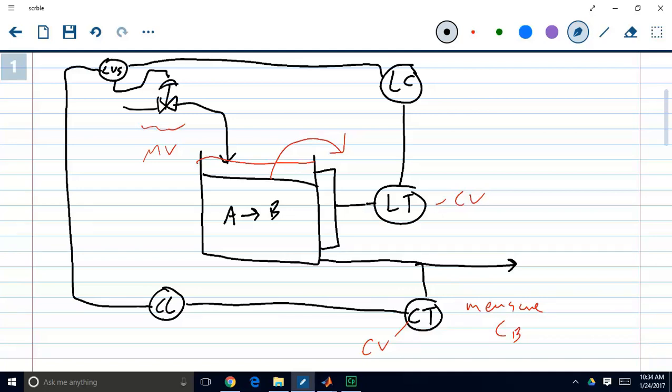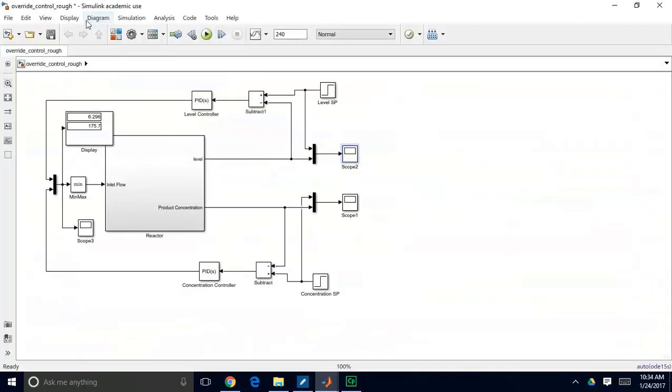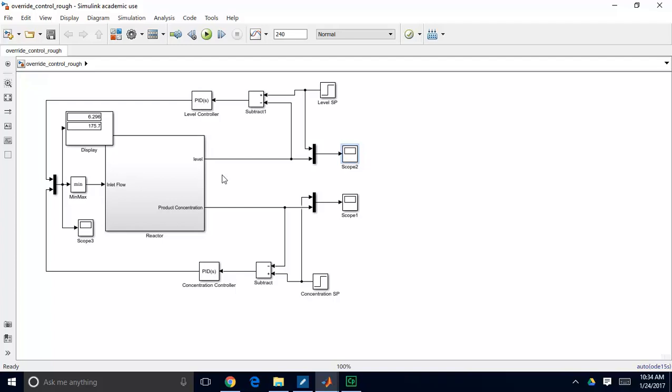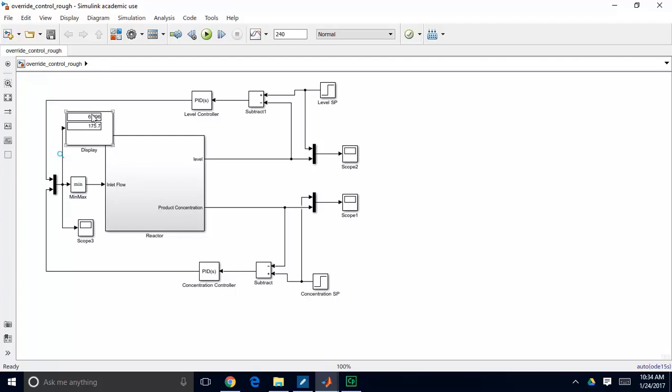So practically, we ran into some issues in our Simulink model. We set up this control scheme. We have our two different controllers that are each tuned to achieve a setpoint. So the level controller tries to achieve a level setpoint, and the concentration controller tries to achieve a concentration setpoint. Those each spit out a recommended flow, and then we pick which of those signals we're going to use by using this minimum block, which just takes those two signals, in this case 6.3 and 176, it picks the lower of the two and implements that.